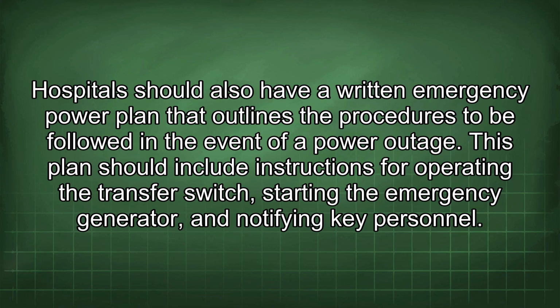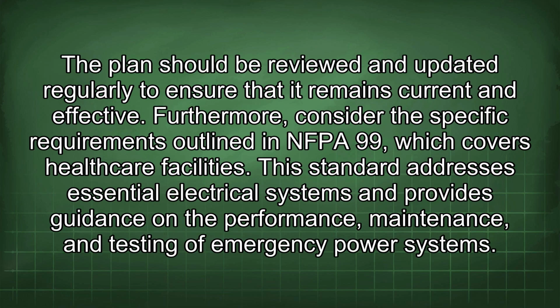This plan should include instructions for operating the transfer switch, starting the emergency generator, and notifying key personnel. The plan should be reviewed and updated regularly to ensure that it remains current and effective. Furthermore, consider the specific requirements outlined in NFPA 99, which covers healthcare facilities. This standard addresses essential electrical systems and provides guidance on the performance, maintenance, and testing of emergency power systems.